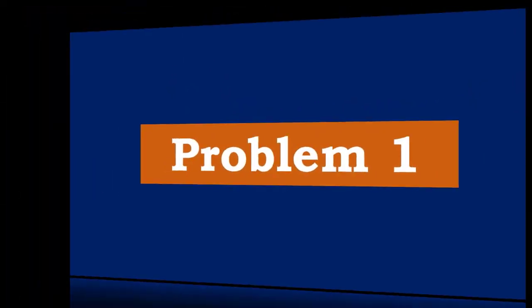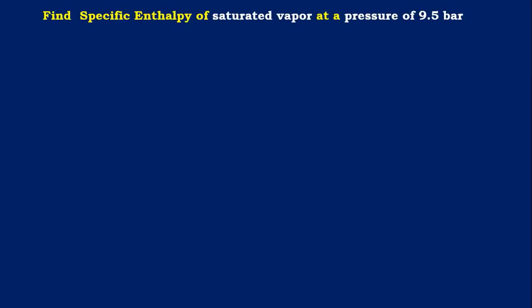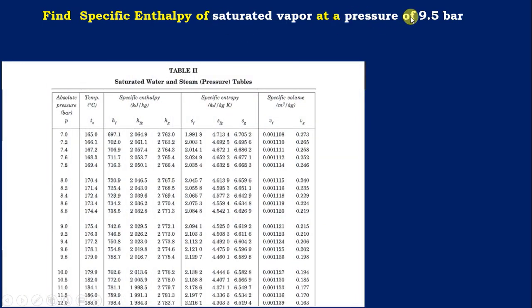Problem number 1: Find specific enthalpy of saturated vapour at a pressure of 9.5 bar. From this we can conclude that the saturated pressure steam table can be used, i.e., Table 2 — saturated water and steam pressure tables. What we need to find out is the enthalpy of saturated vapour, that is Hg, at a pressure of 9.5 bar, which is not available in the steam table. In such a scenario, we have to do interpolation.